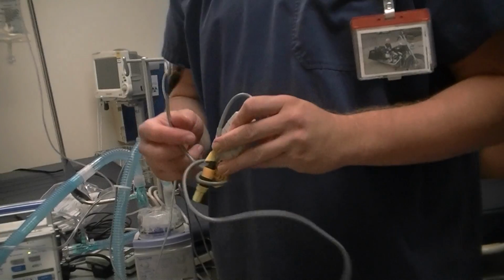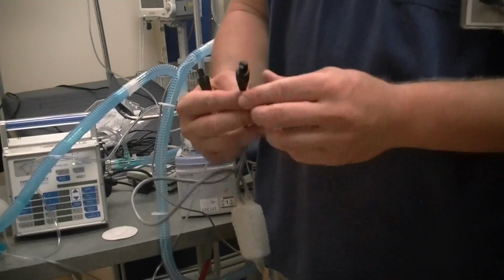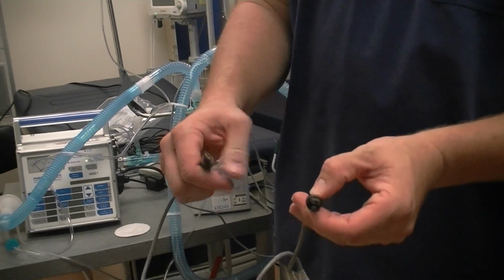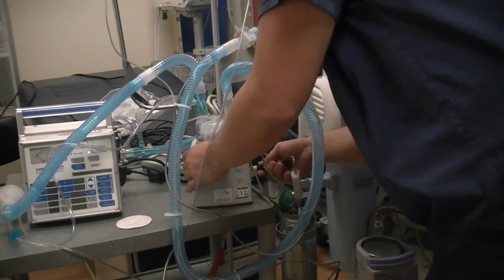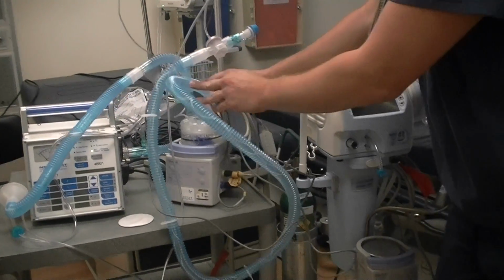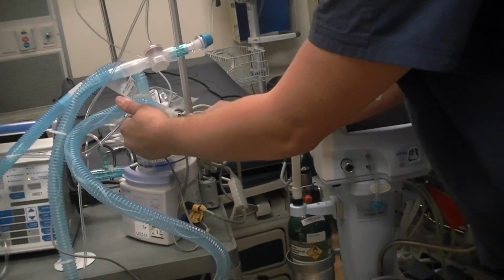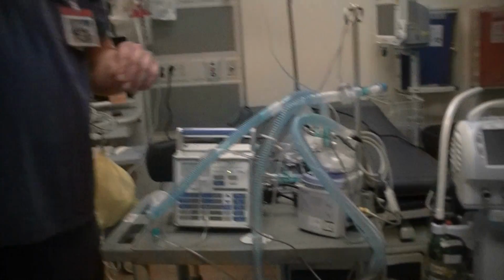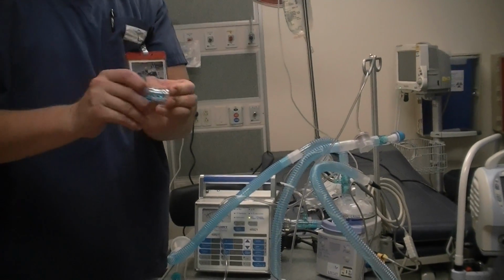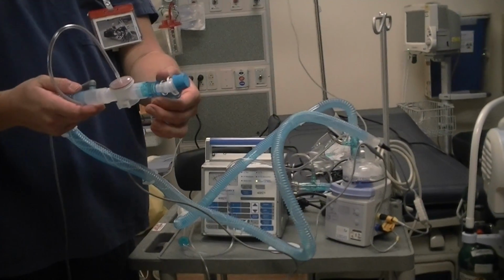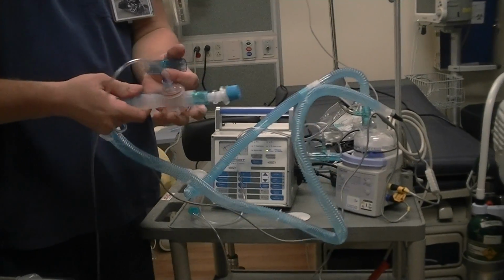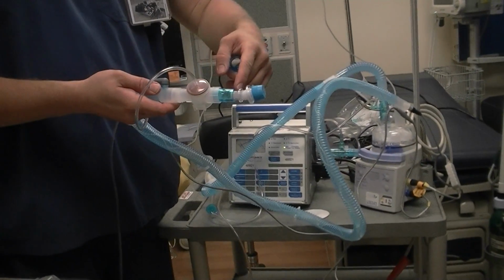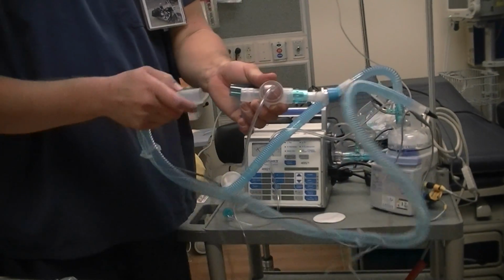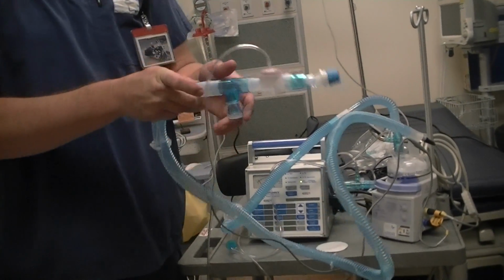Okay, you're going to grab your heater wire. Now in the ICUs, we always use both. In 5 West, we use the one that has the 3 adapters instead of the 2. And this hooks up to the back of your circuit right over here. Alright. So you're going to grab your nebulizer adapter. Make sure it's capped off. Now this, you could either put in front of the exhalation valve or behind it. I recommend you put it behind it only because it'll give you more flexibility. It'll loosen the stiffness on the patient side of it. So I recommend putting it right here.